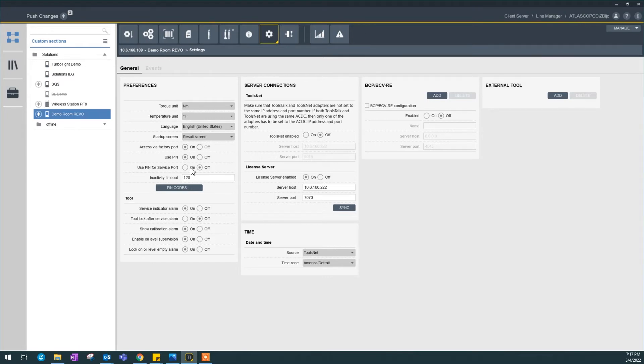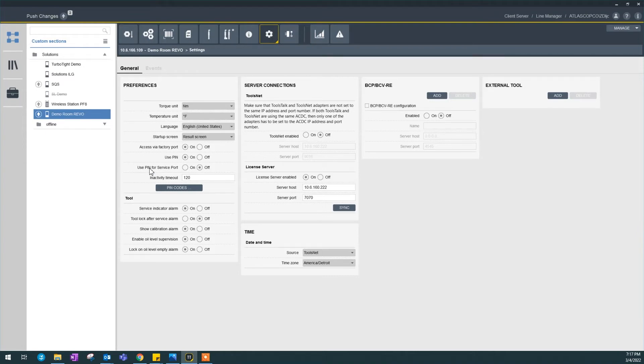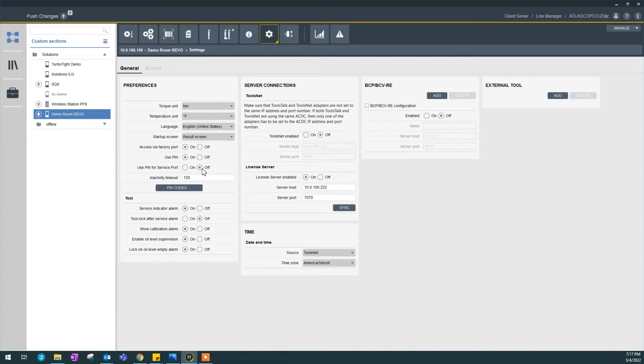Now, this is an interesting option. Use PIN for service port. Now we're connecting through factory port, and that makes sense if you want to use PIN codes. If you're connecting through service port, which is in front of your controller, by default, this is set up as off because it could be a way in your controller in case you forgot your PIN code.